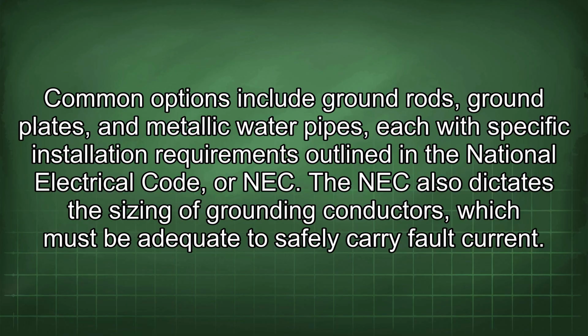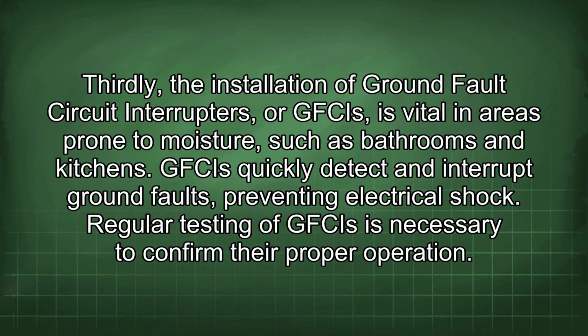The NEC also dictates the sizing of grounding conductors, which must be adequate to safely carry fault current. Thirdly, the installation of ground fault circuit interrupters, or GFCIs, is vital in areas prone to moisture, such as bathrooms and kitchens. GFCIs quickly detect and interrupt ground faults, preventing electrical shock. Regular testing of GFCIs is necessary to confirm their proper operation.